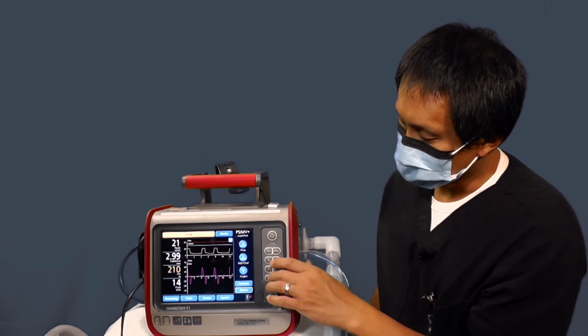All right. I'm going to hit the mode again, and we're going to go through the rest of these modes. Under spontaneous, you have the ability to do pressure support CPAP. So if I hit that button and confirm it, these are your pressure support settings. Same thing as before, that is your delta pressure. Currently it's set at 15, so that would be a PIP of 20. If you want to do straight CPAP, you just turn that down to 0. Confirm my settings, and it switches over.